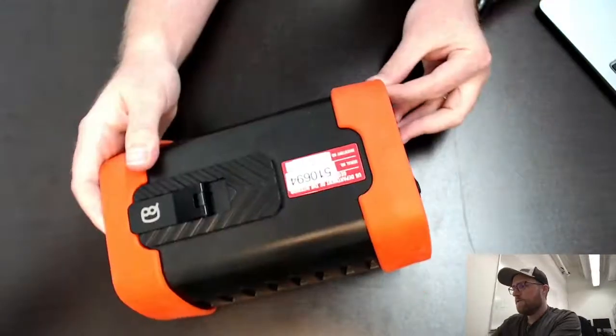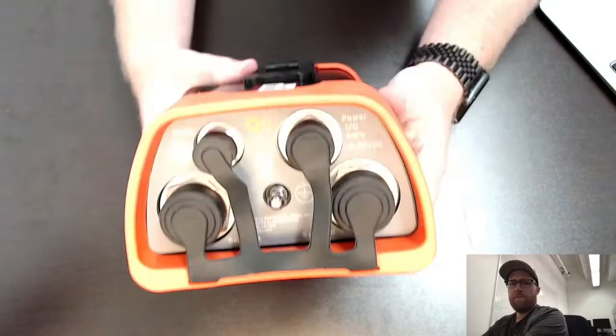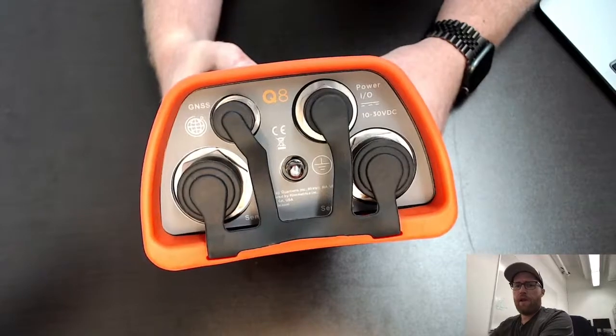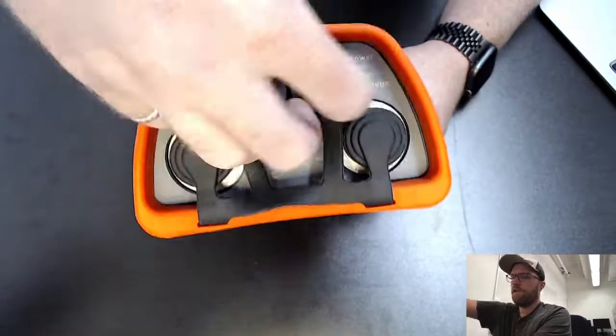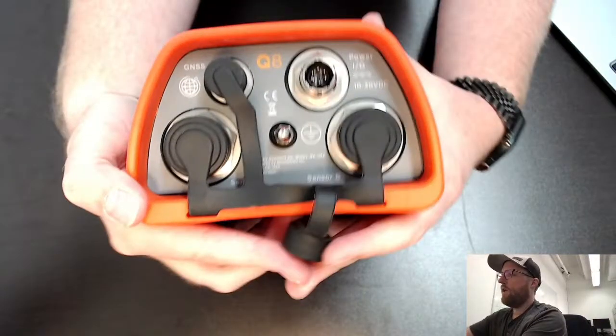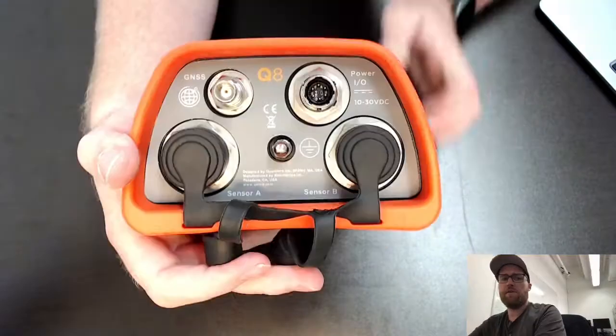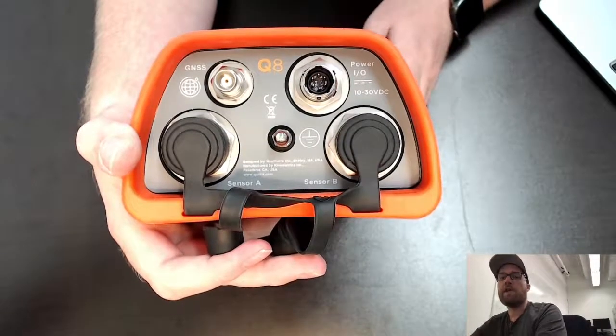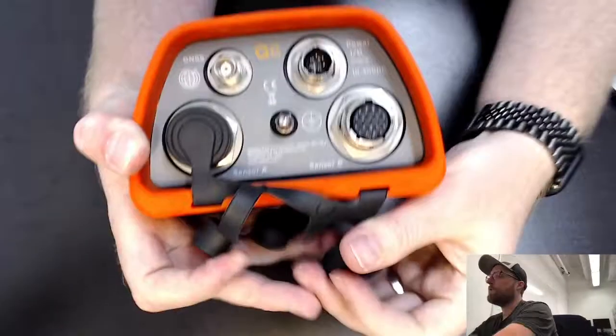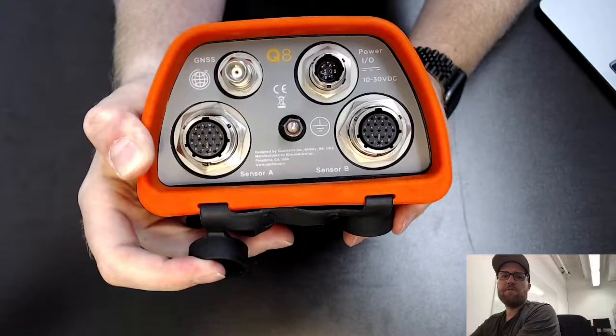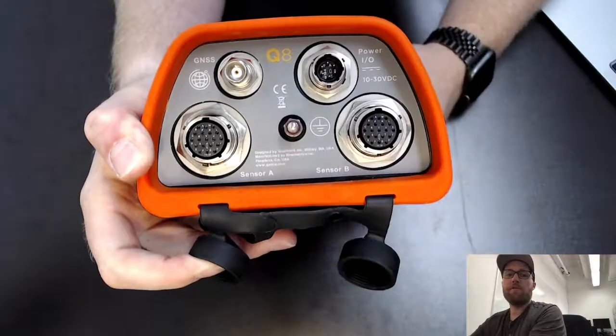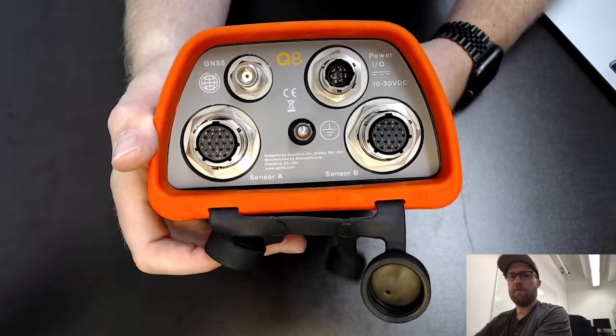So then we have two sides where cables can connect. So this side, this is called the analog side. And we have this power and GNSS antenna. So the GNSS or GPS is used for timing, for getting a very accurate time signal. And then the actual seismic sensors, so the seismometers or accelerometers, those plug into sensor A, sensor B. And then of course your ground, which you should connect if you're using grounding at your station.